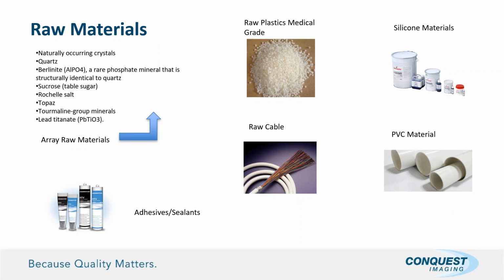So let's talk a little bit about raw materials. Again, in the upper left-hand corner there, you see some of the various crystal-type materials that make up most piezoelectric arrays, PZT arrays, just various raw earth materials that they use to manufacture the actual array crystal. You've got your raw plastics, which typically come in a pellet form like that, and you've got to make sure that's medical grade plastics. You've got silicone materials, again, for lenses or any strain release, other rubber pieces. With the cabling, you've got your raw cable, your microcoax, which has bundles anywhere from 64 to 256 wires. You've got a PVC type of material that encloses the cable jacket. And then you've got a wide variety of adhesives and sealants. All these things really need to be medical grade, and again, that adds cost. I'll talk a bit more on that later.